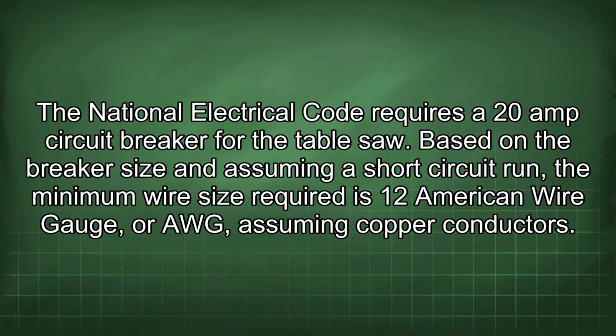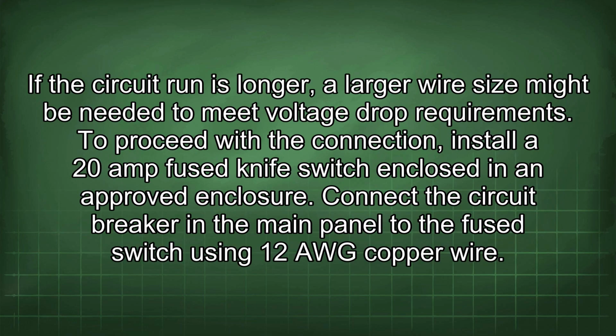The National Electrical Code requires a 20 amp circuit breaker for the table saw. Based on the breaker size and assuming a short circuit run, the minimum wire size required is 12 American Wire Gauge, or AWG, assuming copper conductors. If the circuit run is longer, a larger wire size might be needed to meet voltage drop requirements.